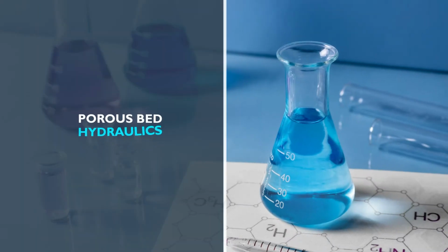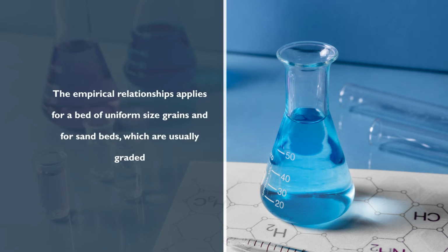Porous bed hydraulics. The hydraulics of flow through a porous bed, which applies to clean filters and to granular activated carbon and ion exchange beds, is usually described by the empirical relationship given by Carman-Kozeny. The empirical relationship applies for a bed of uniform size grains and for sand beds which are usually graded.